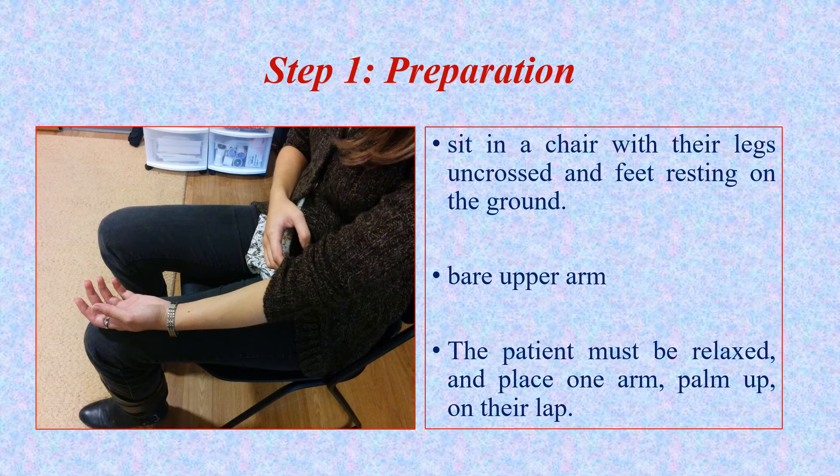The first step is proper patient positioning. Seat the patient on a chair with legs uncrossed and feet resting on the ground. The patient must be relaxed and place one arm, palm up, on their lap. The arm should be relaxed on the desk at the level of the heart.